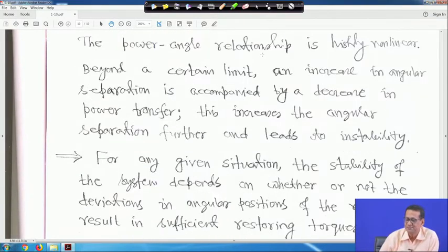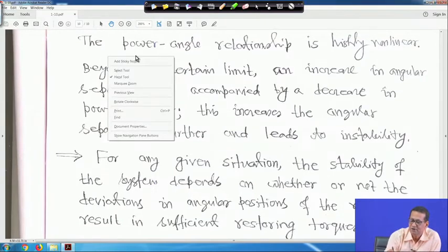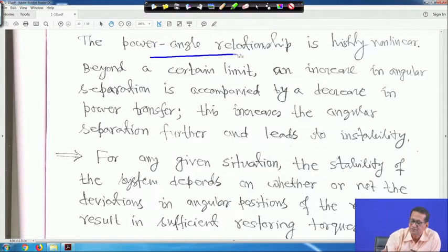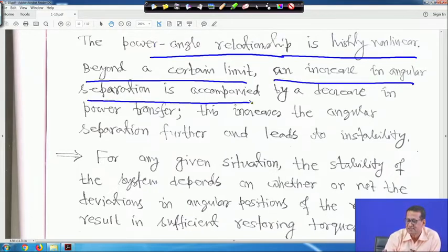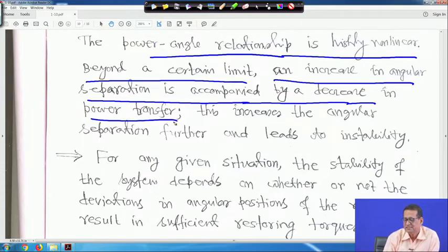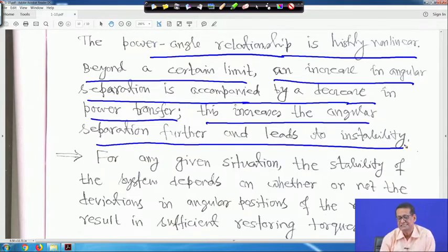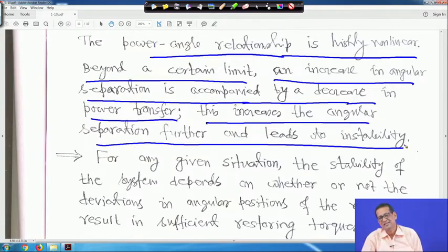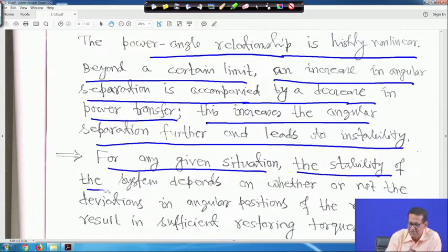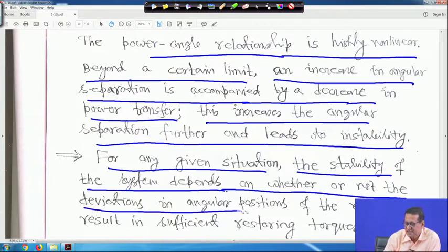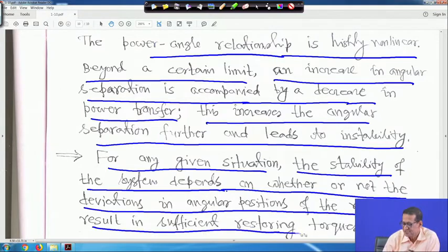The power-angle relationship is highly non-linear — it is a sine function. Beyond a certain limit, an increase in angular separation is accompanied by a decrease in power transfer, which actually increases the angular separation further and leads to instability. For a large system, many other non-linearities are involved. The stability of the system depends on whether or not the deviations in angular position of the rotor result in sufficient restoring torque.